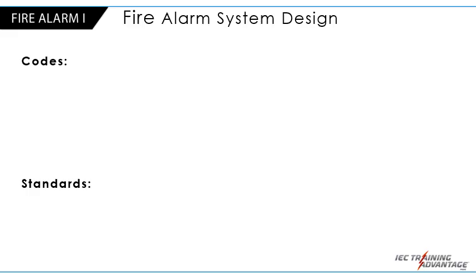When it comes to fire alarm system design and installation, you've heard the terms codes and standards, but both have similar yet somewhat different meanings or requirements. Codes determine the type of system and coverage, whereas standards specify how the system is installed and how it must operate. NFPA 72 is called a code, but is really a standard, with the exception of Chapter 29, Household. NFPA does not specify initiating device or notification appliance coverage for any occupancies except dwellings. NFPA 101, NFPA 5000, or local building codes must be consulted for system and coverage requirements.